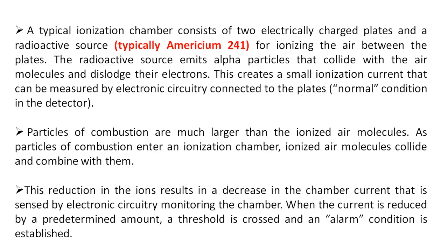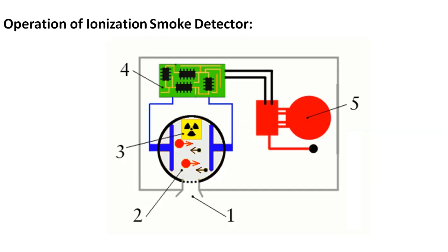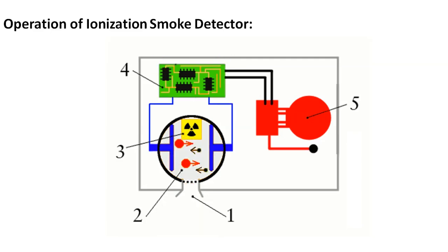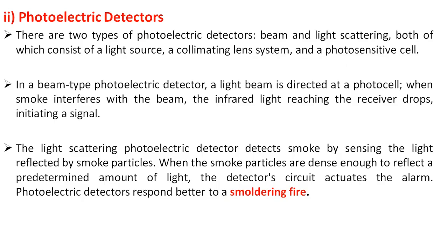Photoelectric detectors come in two types: beam type and light scattering type. Both consist of a light source, a lens, and a photosensitive cell. In the photo beam type photoelectric detector, a light beam is directed at a photocell. The source and sensor are on opposite sides. Under normal conditions, the sensor detects maximum light. Whenever smoke particles enter the detector area, the sensor sees less light, which is detected by the electronic circuit and triggers an alarm.